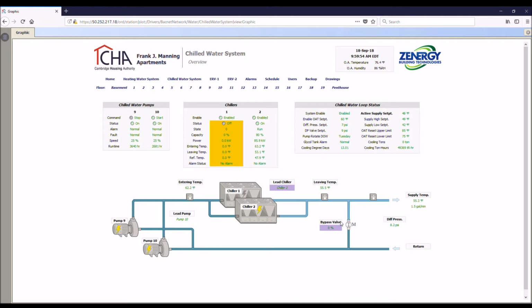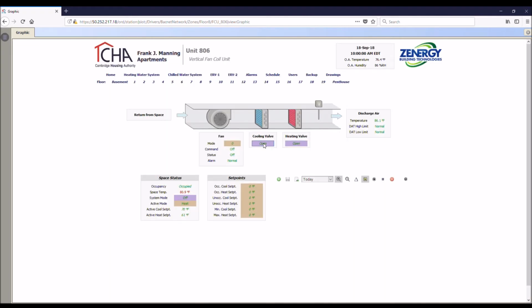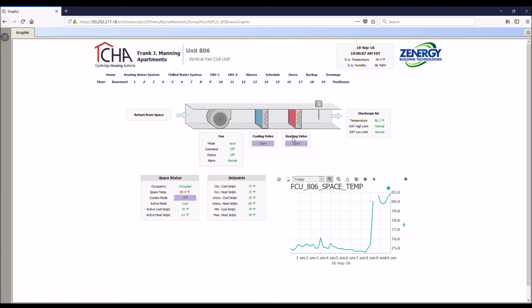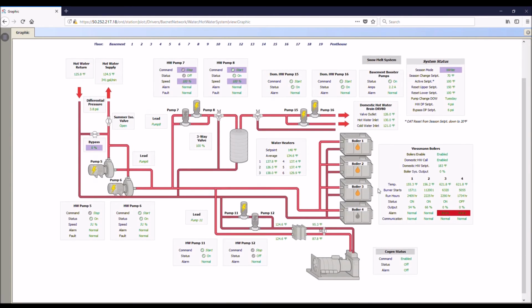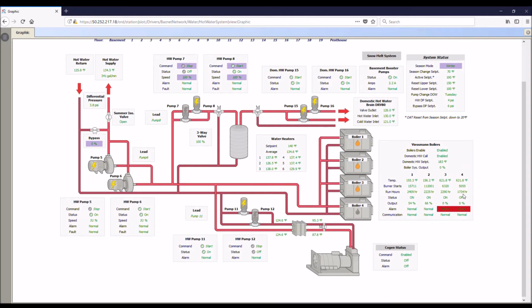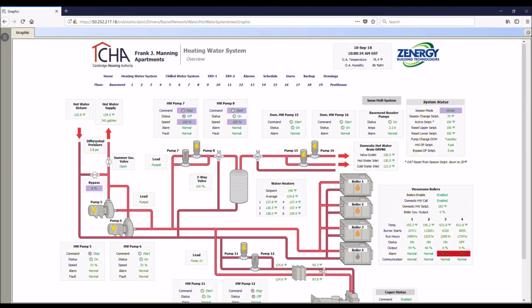You notice we have a lot of overrides currently in, and that's just because we're doing the water balancing. So all of the valves in the building should be open so that we have full flow through all the coils, so we can verify the design for the flows for both heating and cooling. So you'll just see that as we're clicking around, things are overridden and open and off, and not normal operation. And also these boilers went to alarm. But other colors are the actual point color.